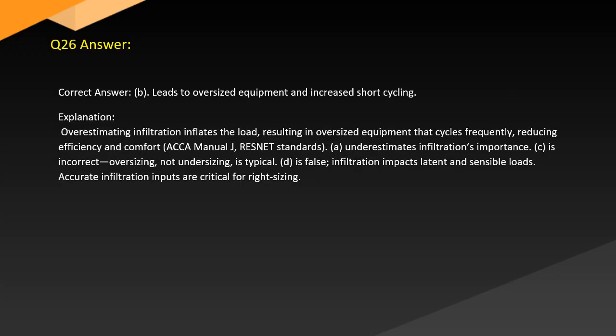Answer. Correct answer. B. Leads to oversized equipment and increased short cycling. Explanation. Overestimating infiltration inflates the load, resulting in oversized equipment that cycles frequently, reducing efficiency and comfort. Manual J, ResNet standards. A underestimates infiltration's importance. C is incorrect. Oversizing, not undersizing, is typical. D is false. Infiltration impacts latent and sensible loads. Accurate infiltration inputs are critical for right sizing.